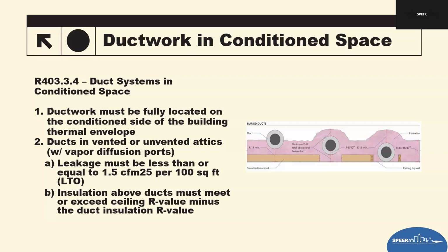The first requirement is straightforward. If you're claiming ducts are inside conditioned space, they truly have to be completely inside the thermal envelope, not partially, not mostly, but fully located in the conditioned boundary. This eliminates the old practice of calling ducts inside conditioned space just because the attic has a vapor diffusion port or has been encapsulated with foam. There are special rules for ducts in vented and unvented attics. Now, if you're doing buried ducts, there are all these rules you can go through. I won't go through all of that.